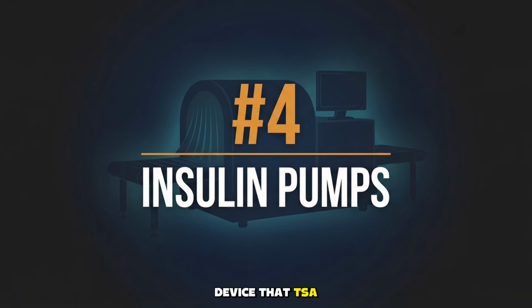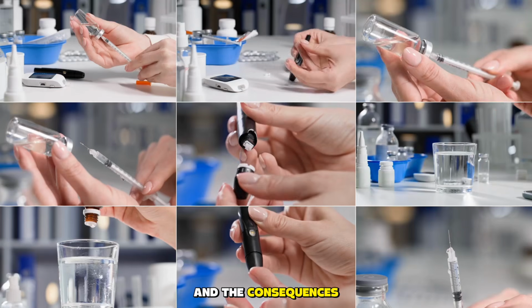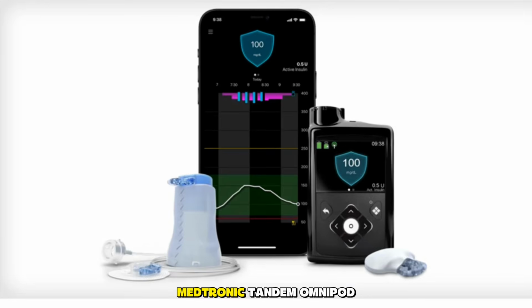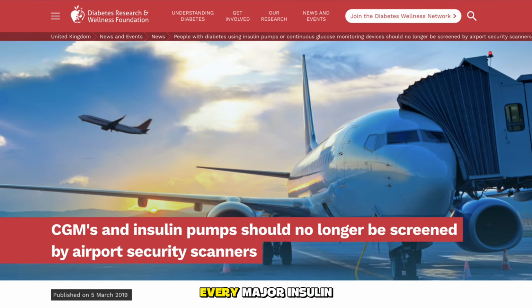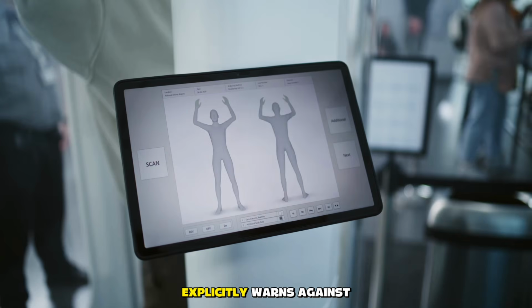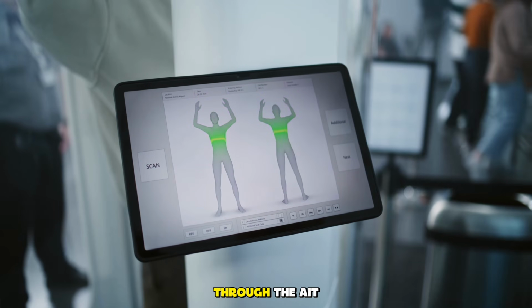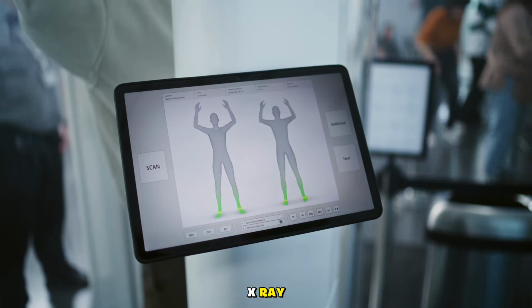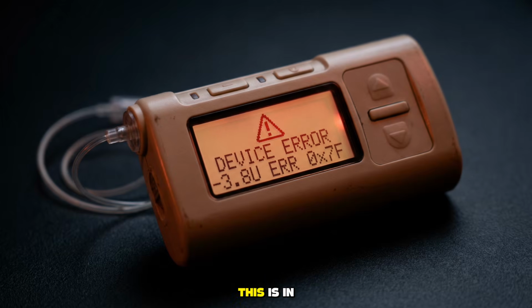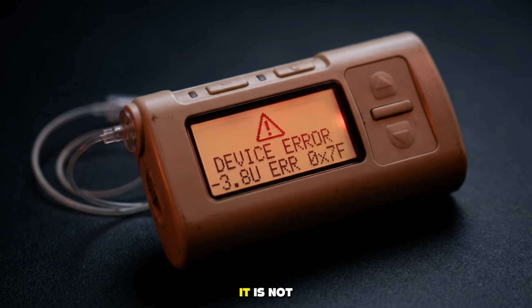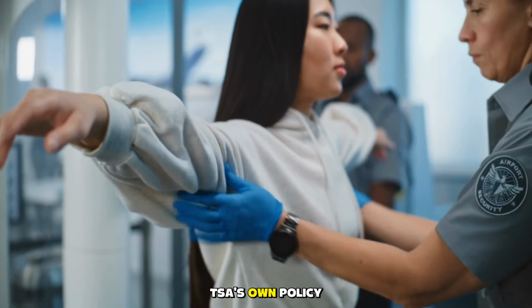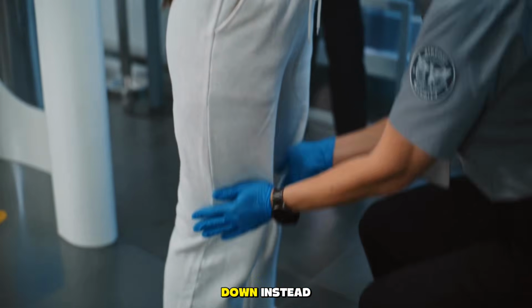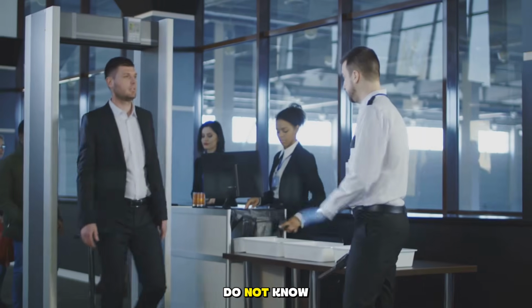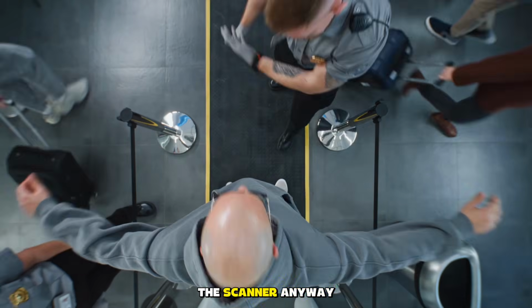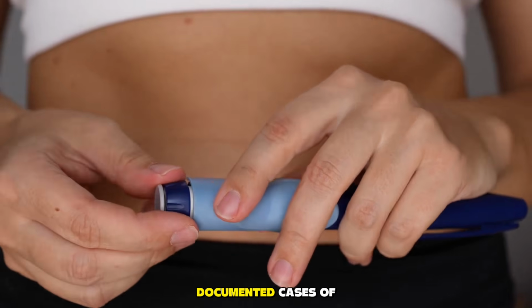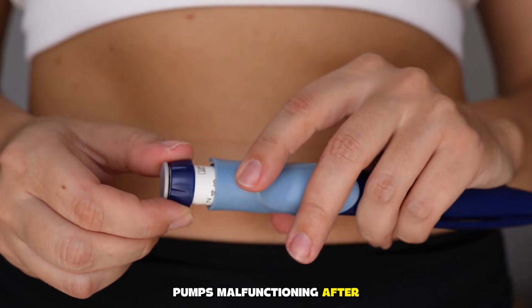This is the device that TSA agents keep getting wrong, and the consequences are not minor. Medtronic, Tandem, Omnipod, every major insulin pump manufacturer explicitly warns against sending their device through the AIT body scanner or X-ray. The radiation can damage the pump. This is in the manufacturer documentation. It is not a rumor. TSA's own policy says passengers can request a pat-down instead, but agents frequently do not know this and pressure passengers to go through the scanner anyway. There are real documented cases of pumps malfunctioning after screening.